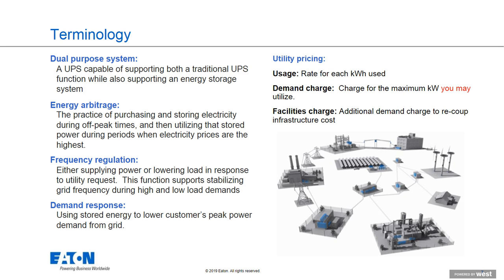Another possibility is frequency regulation, where these distributed energy resources, usually many working in concert, can be used to feed power back onto the grid if necessary, or draw extra power from the grid, with the purpose of regulating the utility company's frequency.